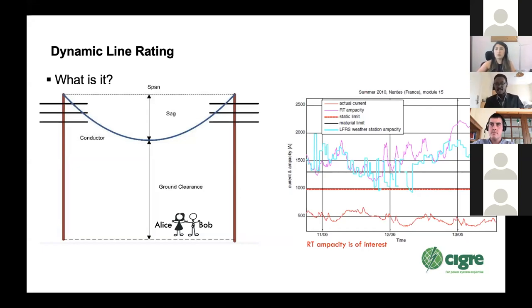So the ground clearance basically is the distance from the minimum point of the conductor to the ground. And in determining the ground clearances, there are several environmental factors that are considered. These factors are usually very conservative, to ensure that the clearances are never exceeded. So we usually assume very high temperatures, for example, very low wind speeds, and the maximum amount of solar radiation, approximately 1,000 watts per meter squared, usually.